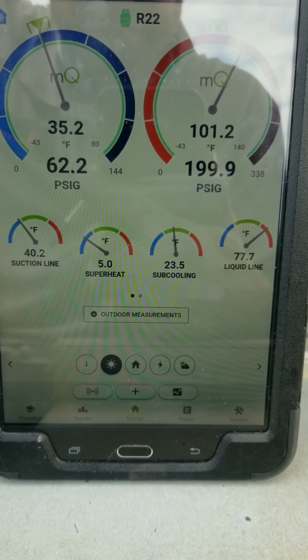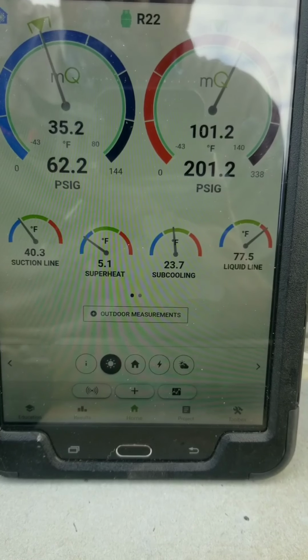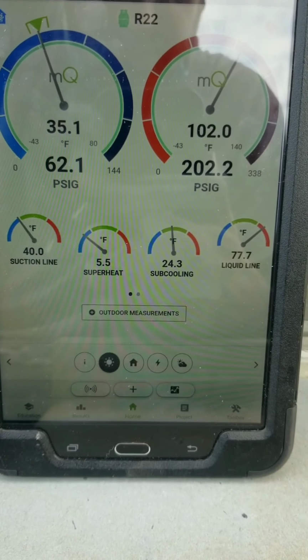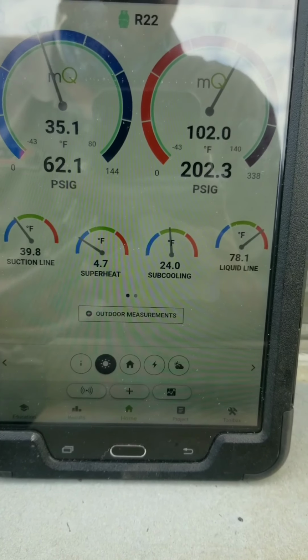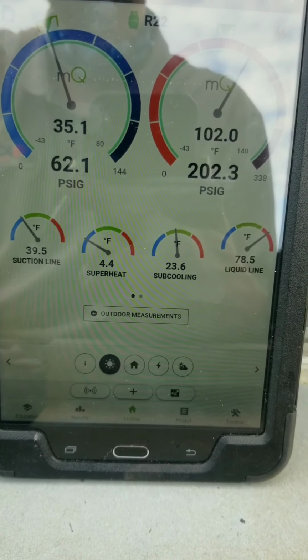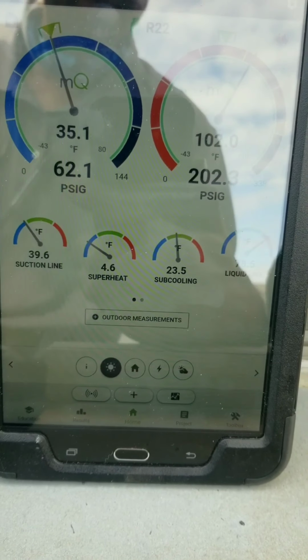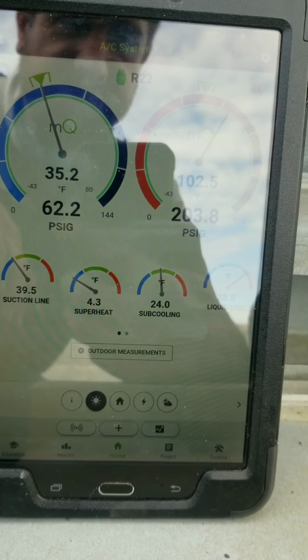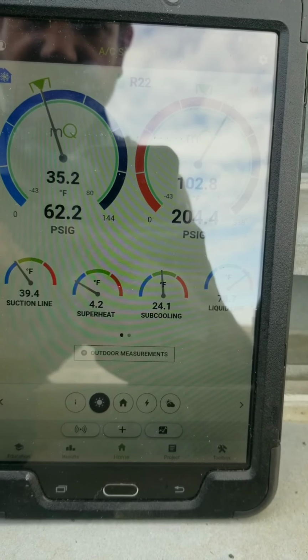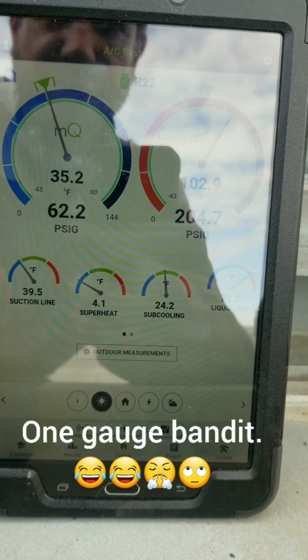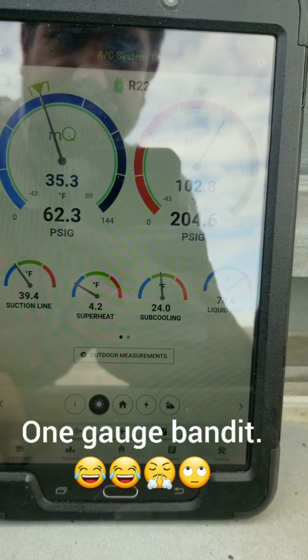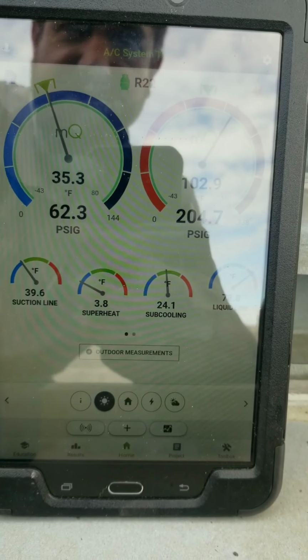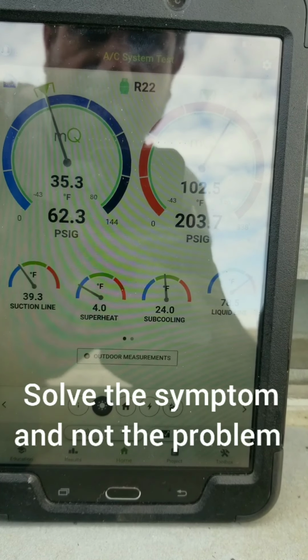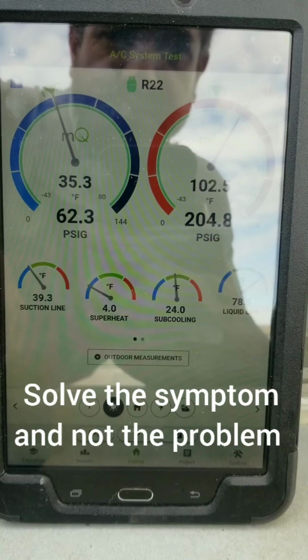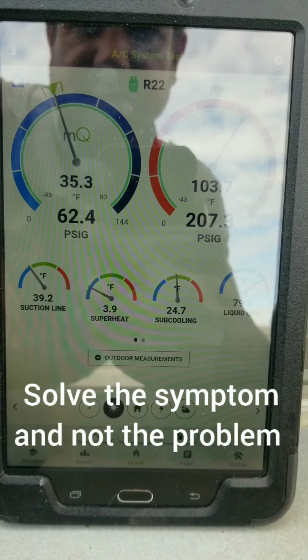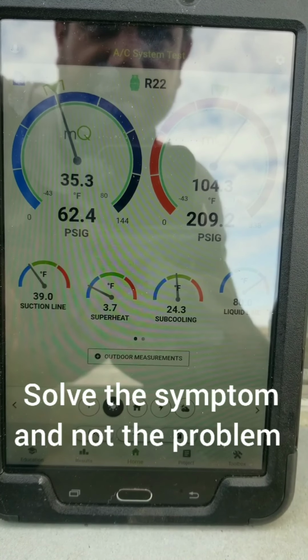Subcooling a little high and the superheat dropping. What we could have going on is we could be overcharged. A lot of times with these Carrier units, the oil breaks down over years of the coils being dirty and start to get a waxy buildup. It'll actually plug up the fixed orifice metering device. So if that header's plugged up, a lot of people come out and say, oh, my suction pressure's low, and dump some charge into it. And they solve the problem, but don't really diagnose the actual issue of the metering device. So that might be what's going on here, if I had to guess.